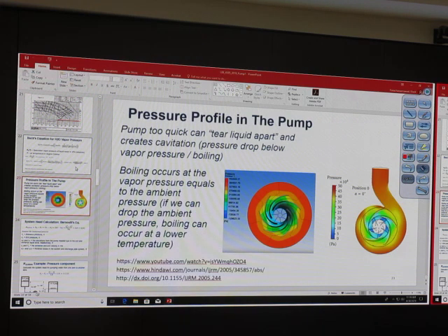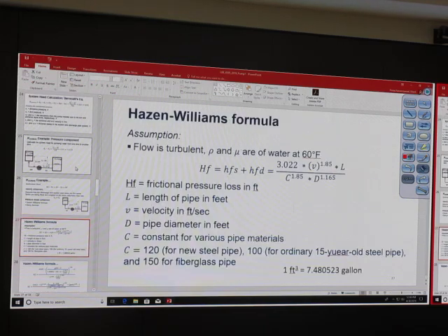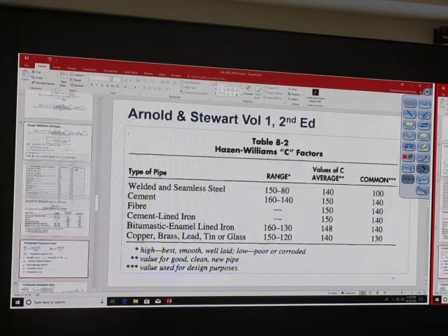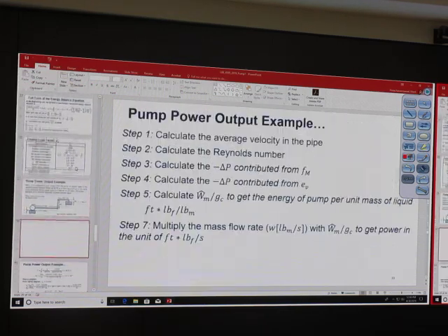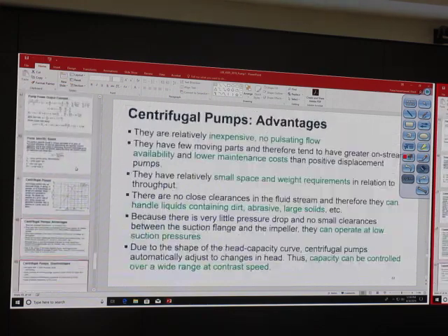Vapor pressure, I think we take quite a bit of time to discuss that hot fluid is more difficult to pump, right? Because it has higher vapor pressure. You remember that? Yes. Why is that? Is that because it's decreased NPSHA? Let's take a look at the equation. Equation for NPSHA.